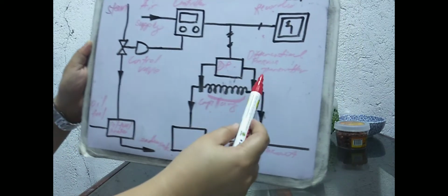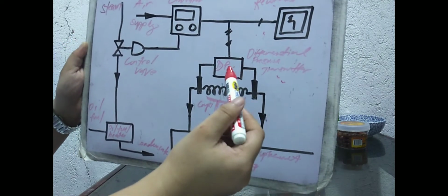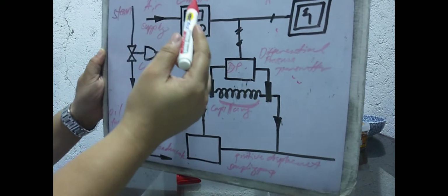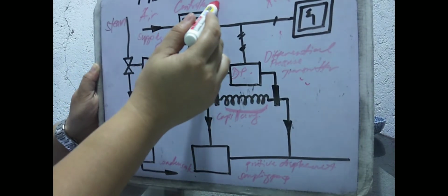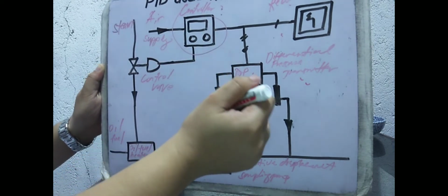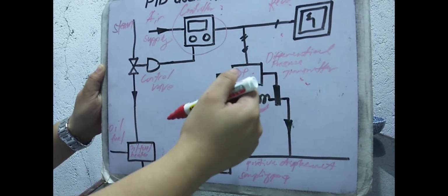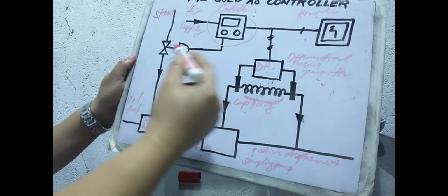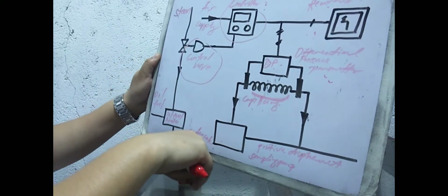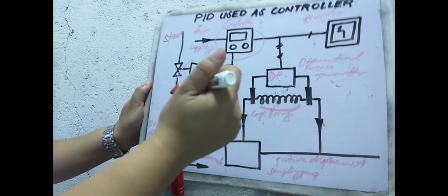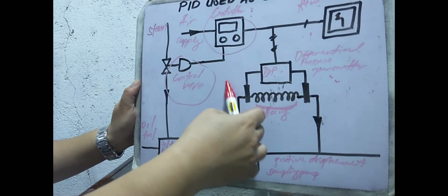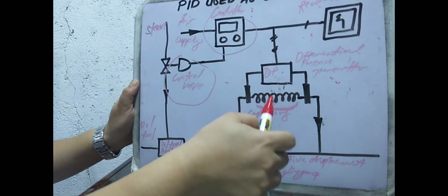A differential pressure transmitter provides analog viscosity to a pneumatic controller. This is the air controller, which regulates the supply of fuel heating steam through a control valve. So that's our entire system. It just shows the fuel pumped at a constant rate through a fine capillary tube.